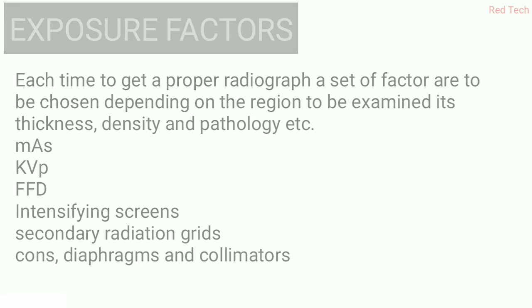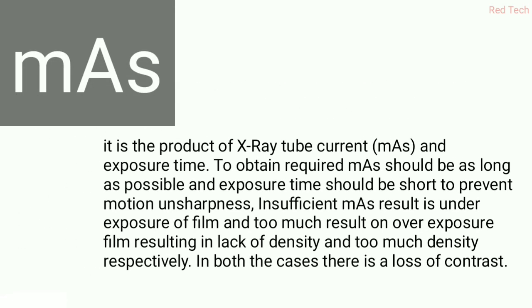First is MAS. MAS is the product of x-ray tube current and exposure time. The current flowing in the x-ray tube is measured in milliampere, and the time taken for exposure is in seconds, so we call it milliampere-second (MAS).